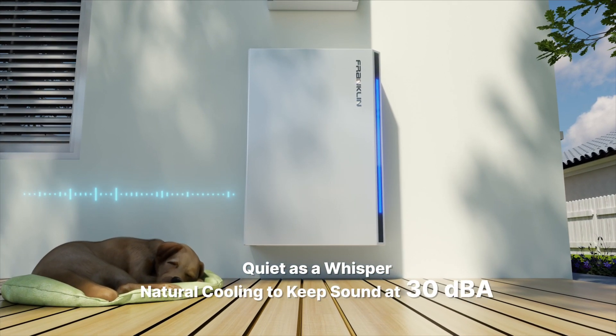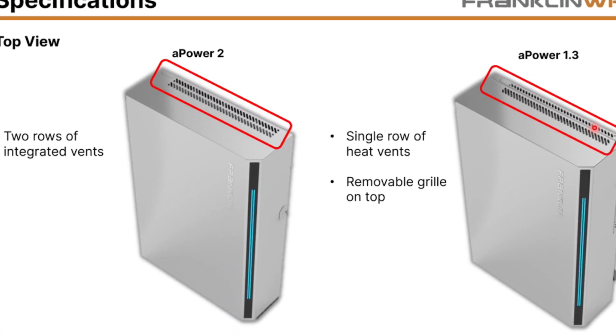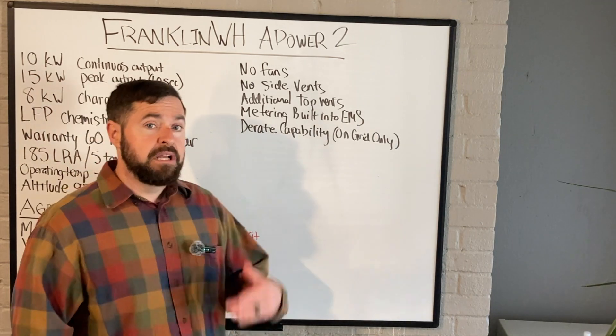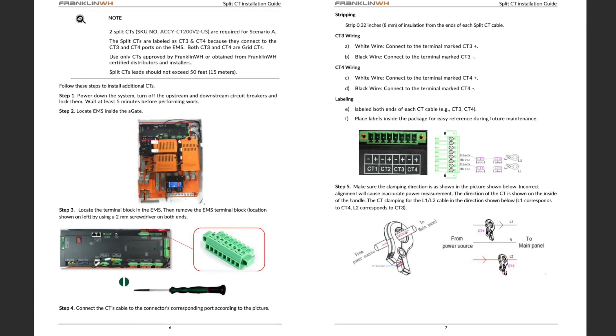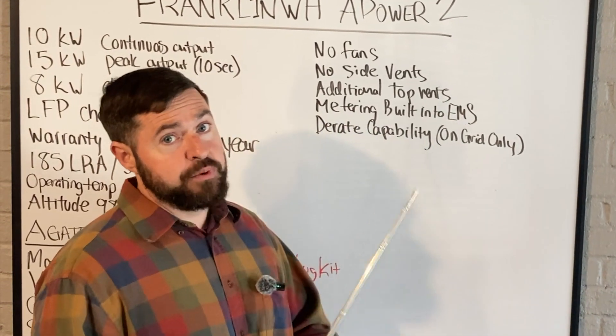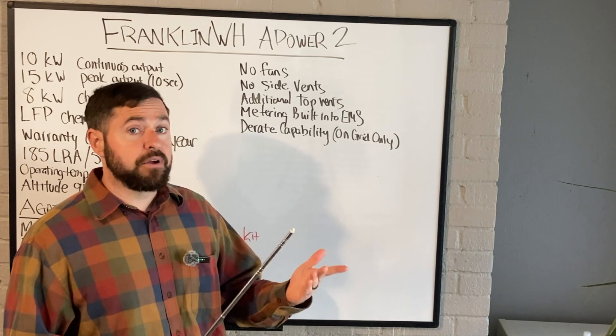Some other new features: they've removed fans from the A-Power 2 — that's one form of potential equipment failure gone. There are no vents on the sides of the A-Power 2; we've got additional vents on the top. The metering is now built into the energy management system — there used to be a little separate energy meter at the bottom of the A-Gate, now it's integrated at the top with the rest of the energy management system. That has opened up more conduit entries on the side of the A-Gate and also changed the CT installation requirements for split systems or complex electrical configurations.